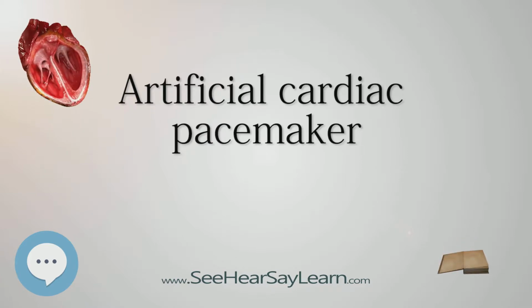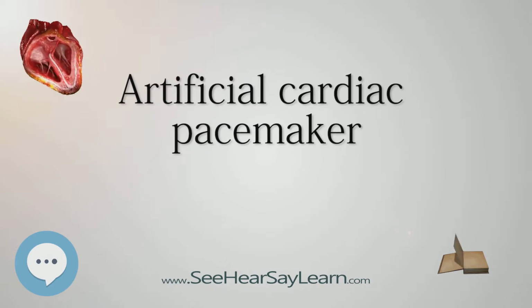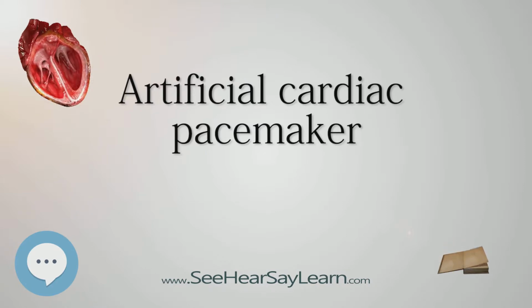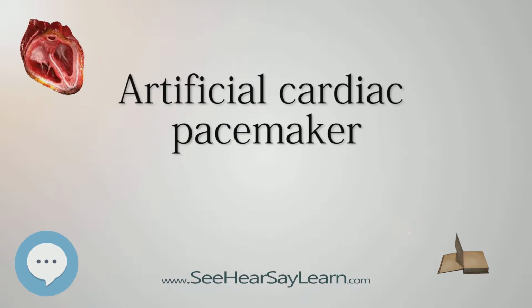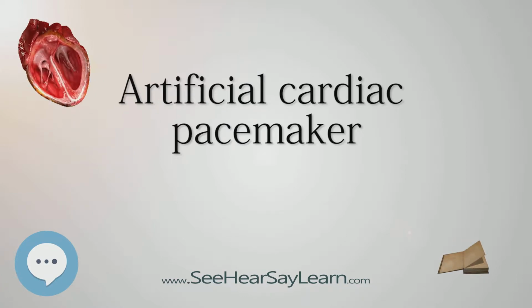Advancements in function. A major step forward in pacemaker function has been to attempt to mimic nature by utilizing various inputs to produce a rate-responsive pacemaker using parameters such as the QT interval, PO2 and PCO2, dissolved oxygen or carbon dioxide levels in the arterial venous system, physical activity as determined by an accelerometer, body temperature, ATP levels, adrenaline, etc. Instead of producing a static, predetermined heart rate, or intermittent control, such a pacemaker, a dynamic pacemaker, could compensate for both actual respiratory loading and potentially anticipated respiratory loading.